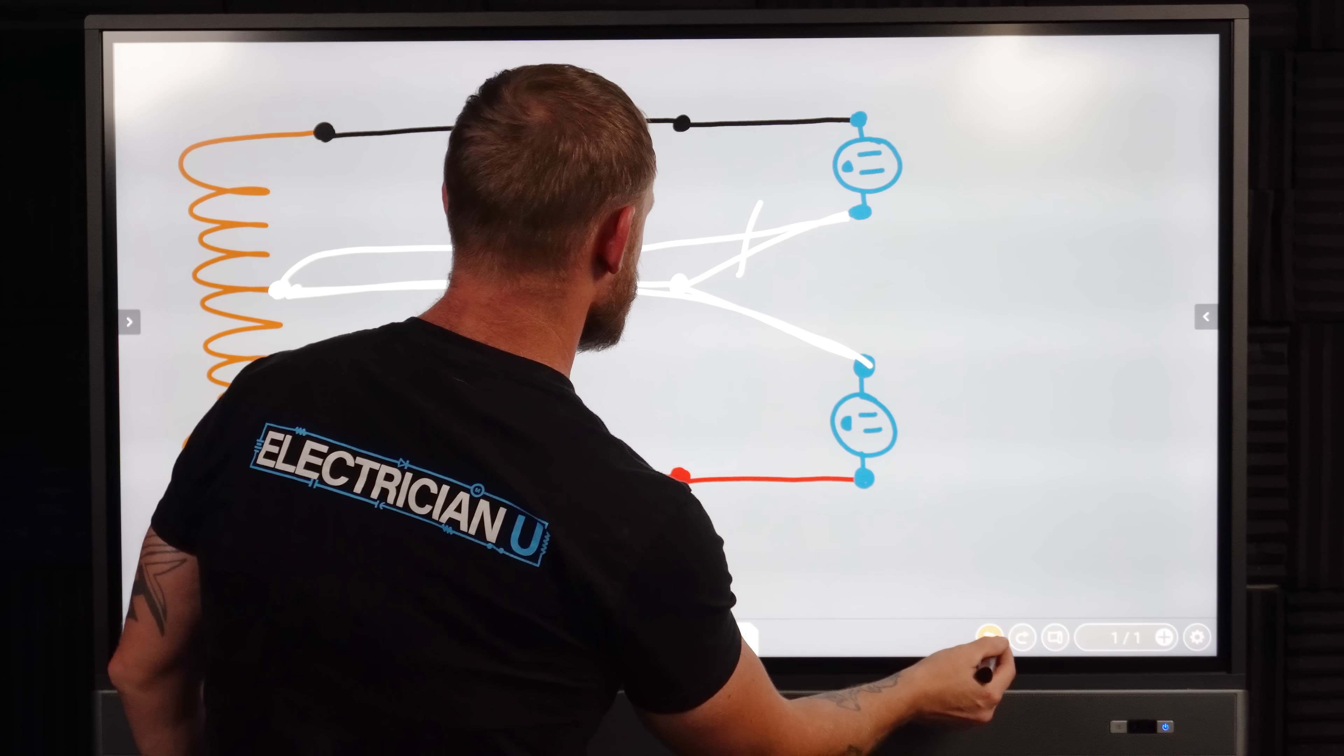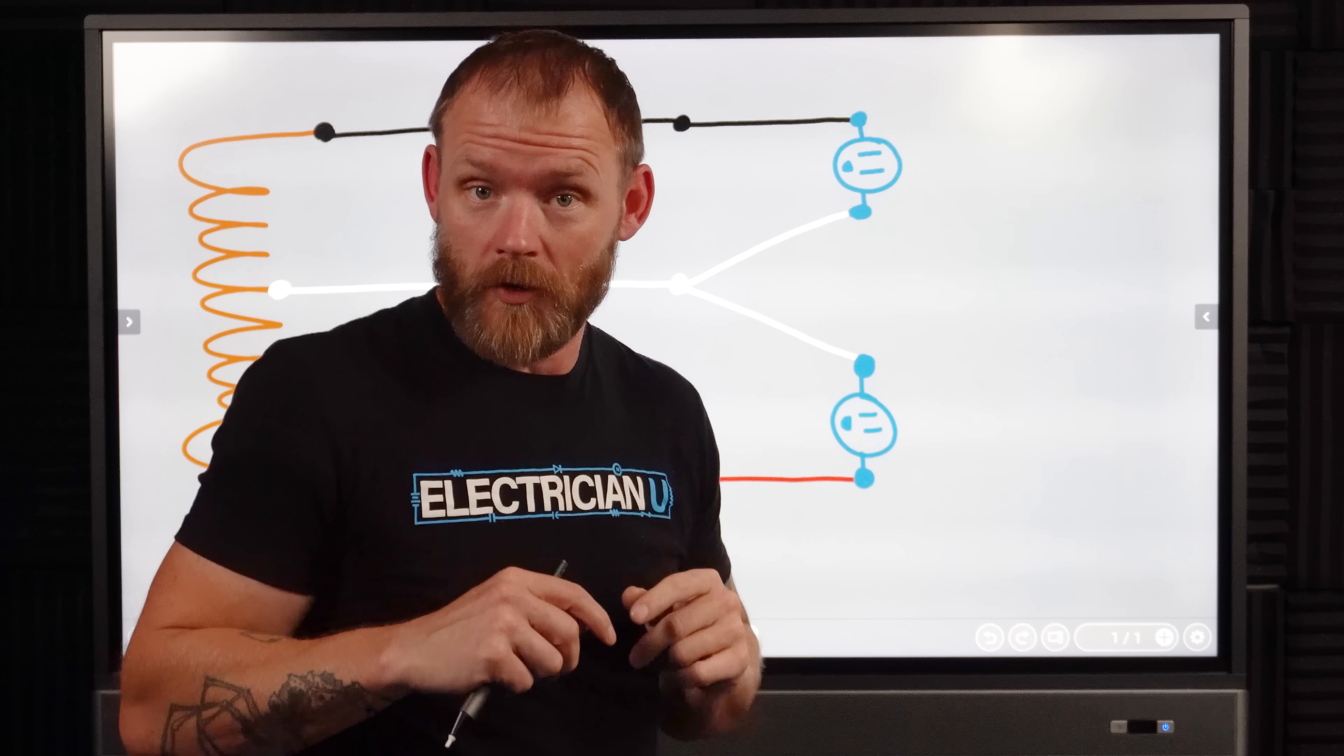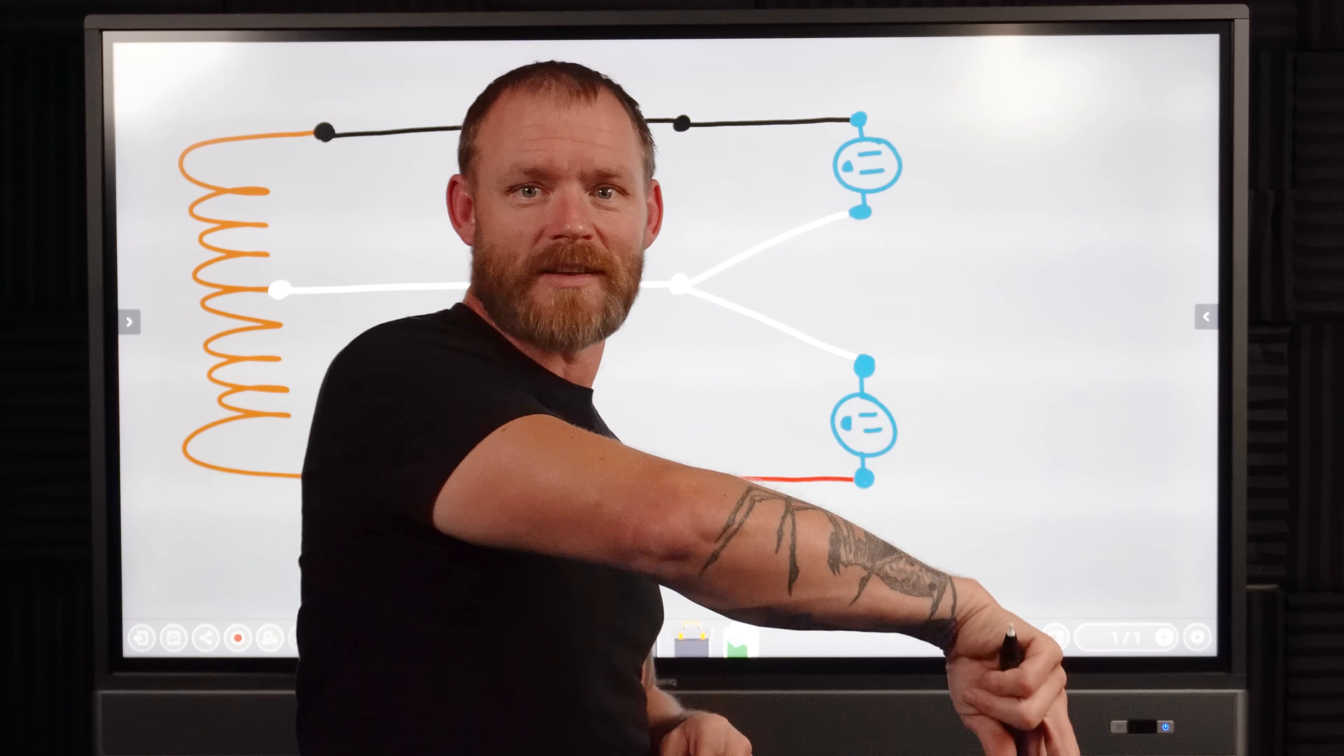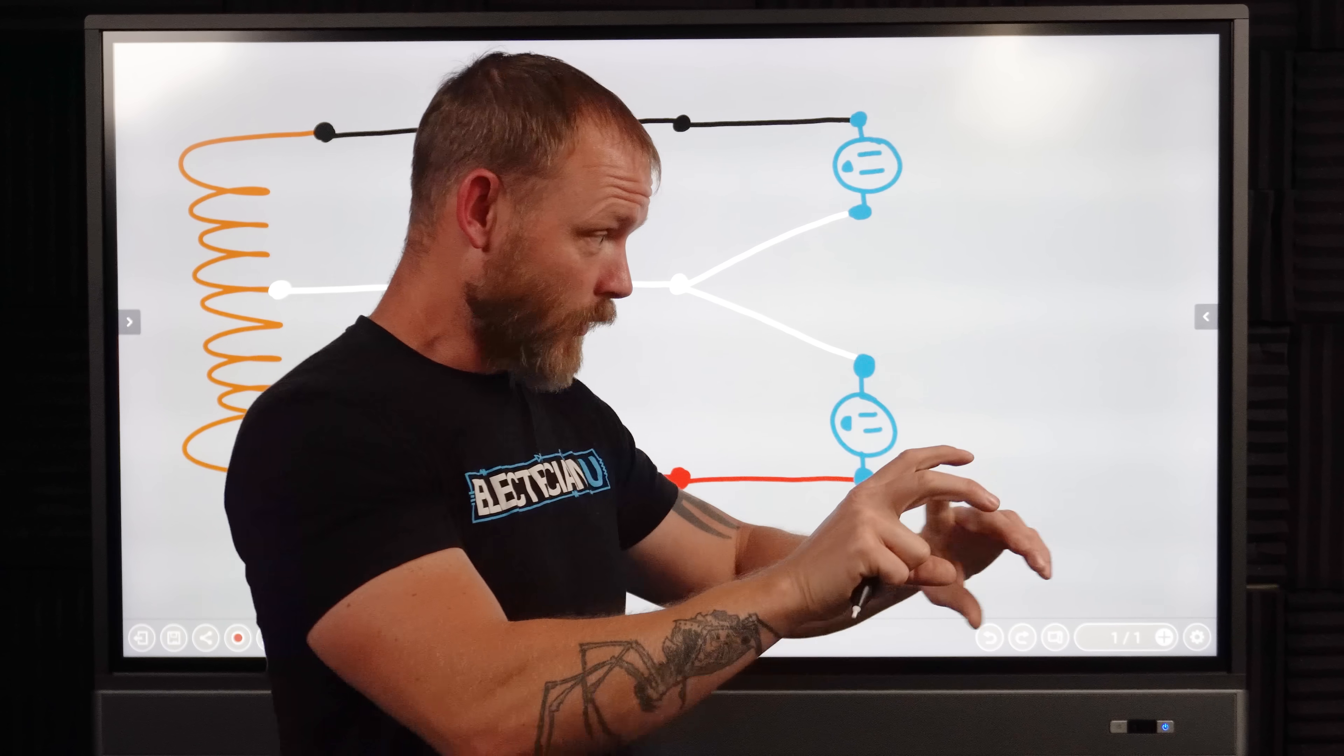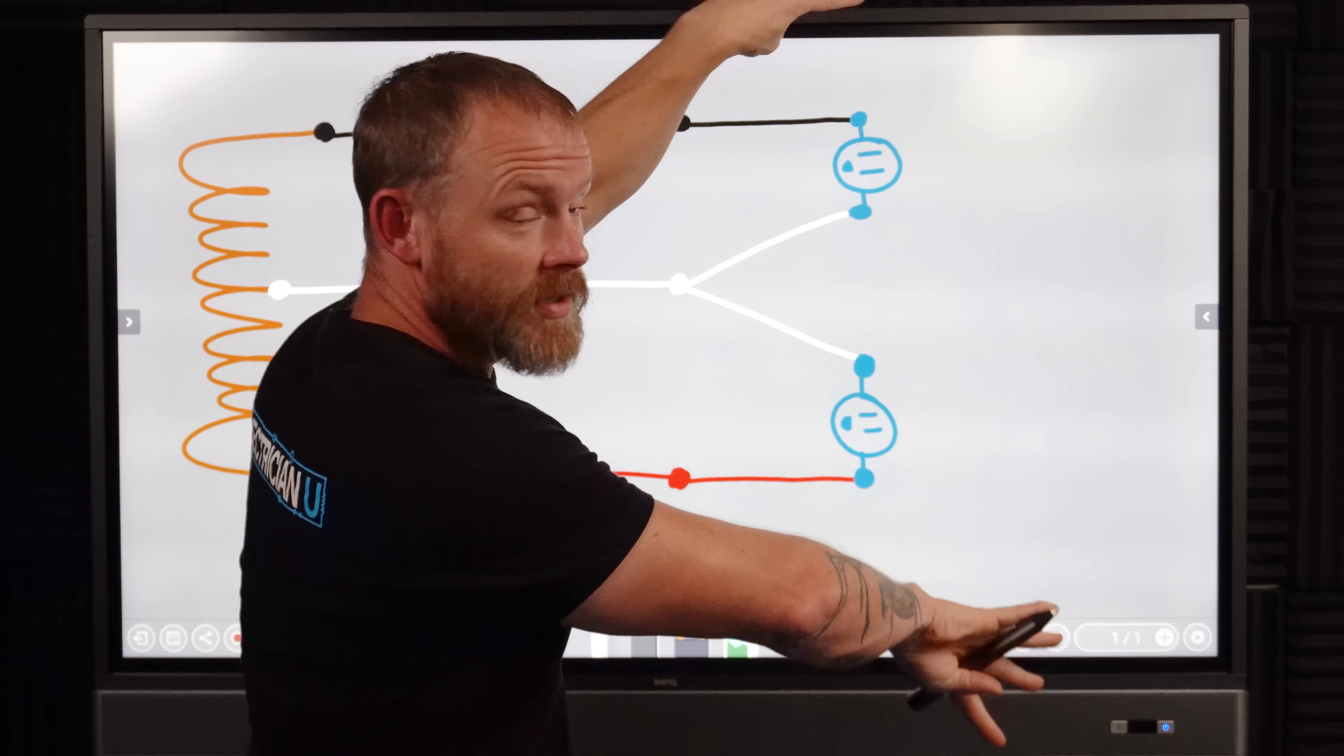But if we have a shared neutral situation, say we have a 12 three, a lot of older homes, like seventies era, eighties era, they would run 12 threes from their panel outside and run them everywhere just to save one conductor. You know what I mean? Saving that one conductor was cheaper than doubling up the amount of 12 two that you're running through a house. So a lot of GFI circuits in kitchens and things like that, that are kind of close to each other. They would just make joints in the back of a junction box, put one circuit worth of plugs on one, and then you would just pass the other circuit through onto something else. So we have a shared neutral.